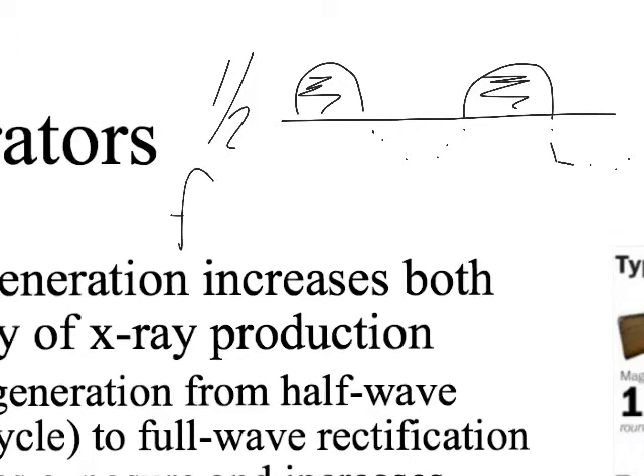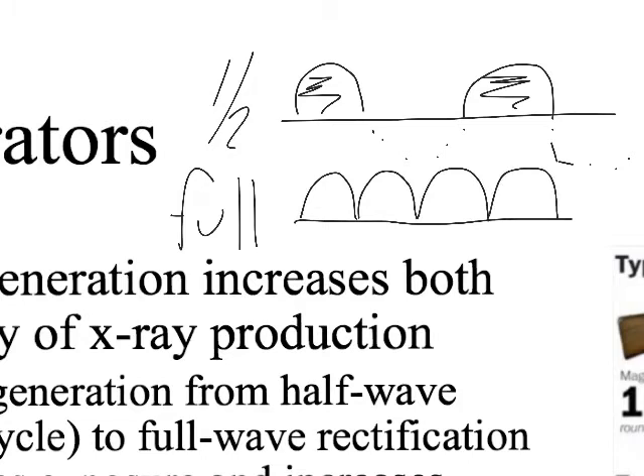Versus full-wave rectification — now we've got something more like the machine gun. We were able to flip the negative part of the wave up over the line, so we've increased the frequency of firing. We've increased the quantity of photons being produced and also the quality. Right now let's focus on just the quantity.